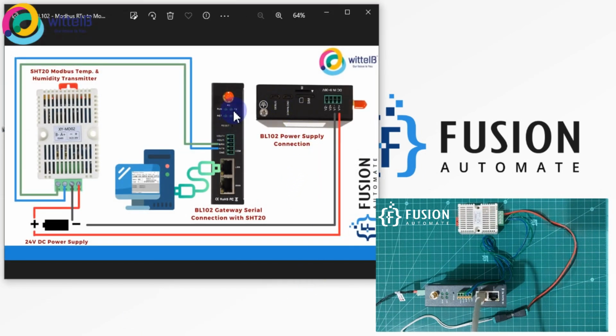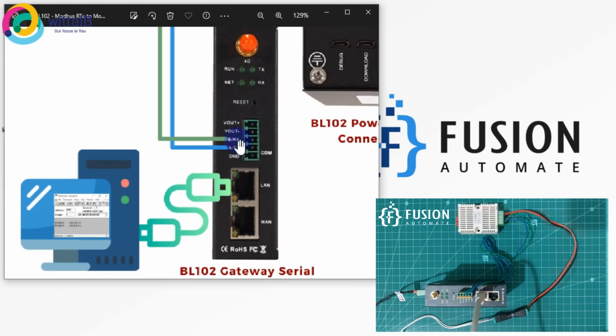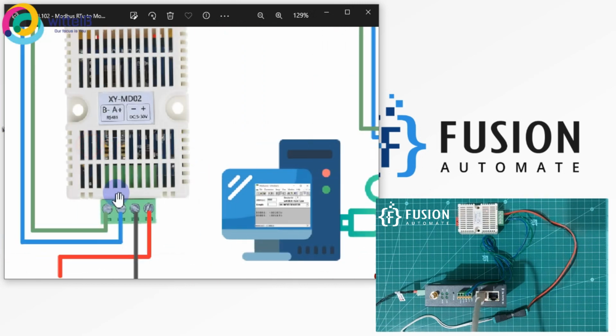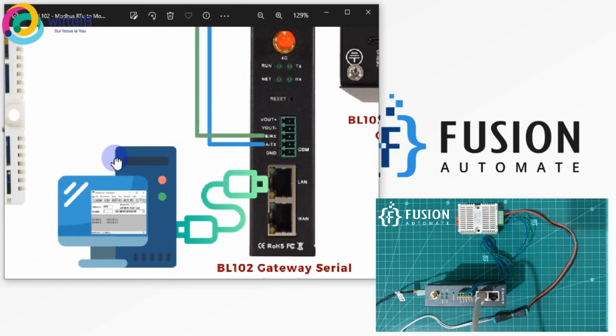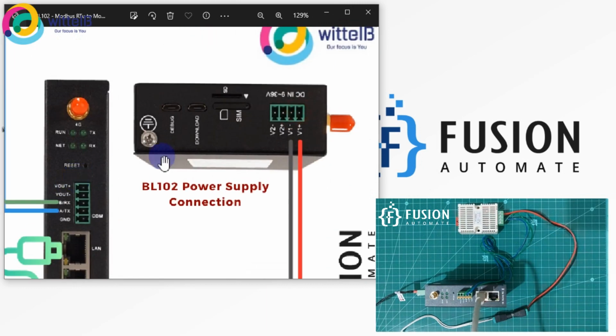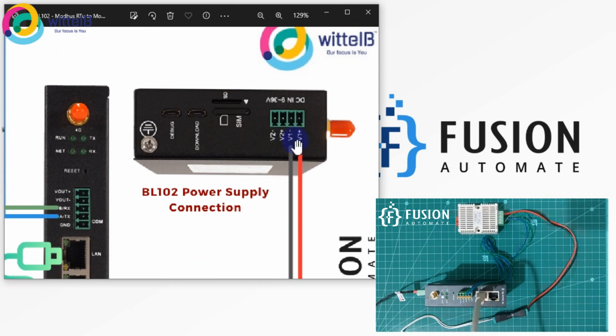So this is our BL102 gateway, and this is our SHT20 Modbus temperature and humidity transmitter. We have connected B minus with the B connection of the BL102 gateway, and this A plus connection is connected with the A or TX connection of this gateway. And this is the power supply connection. We have connected 24 volt with V1 plus and V1 minus.